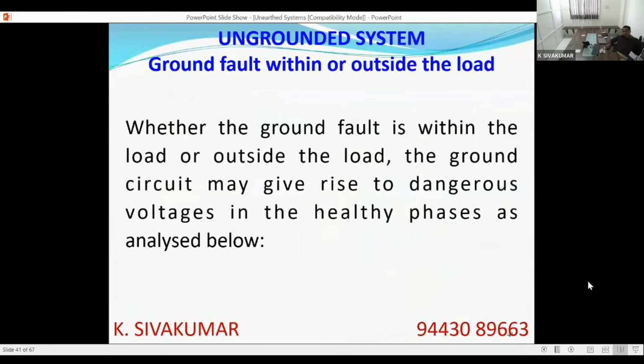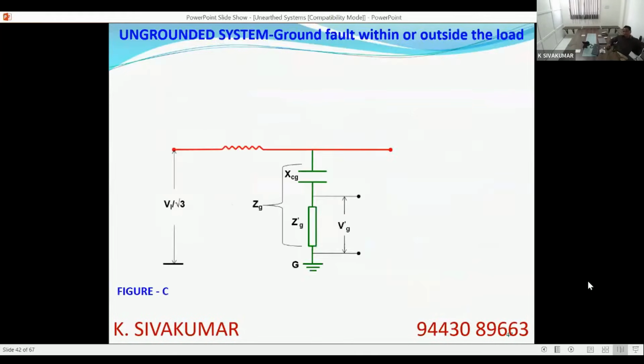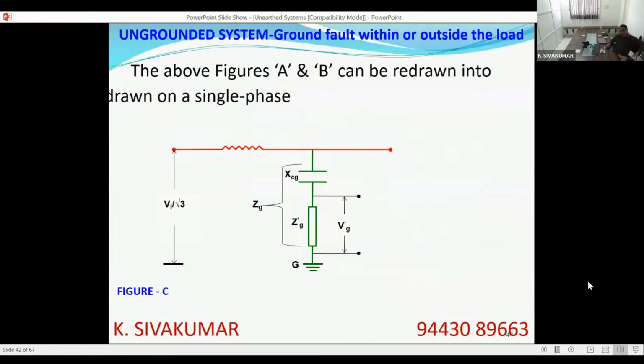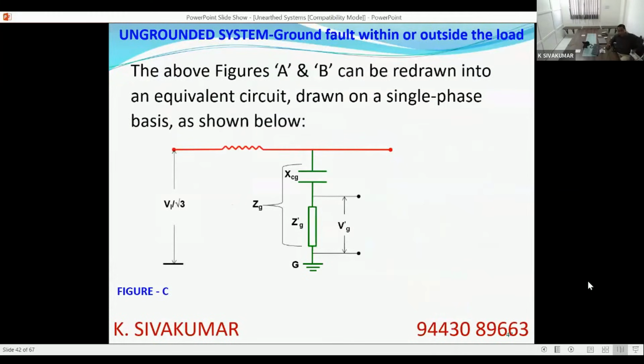So now, as you have seen in the above two diagrams, whether the fault is within the equipment or outside the equipment, there will be added impedance in the earthing circuit. If you draw the equivalent circuit of this added impedance, you can see the voltage to earth is VL by root 3. There is a network impedance, resistance is there, and ZG is the new impedance introduced into the ground circuit by the fault.